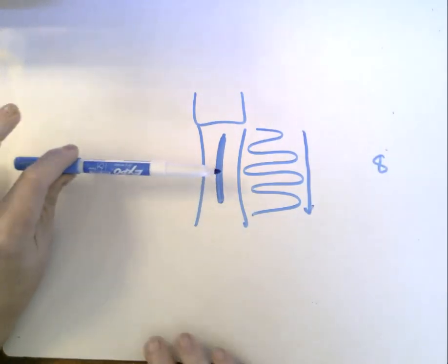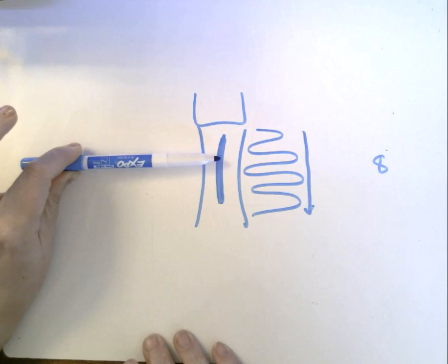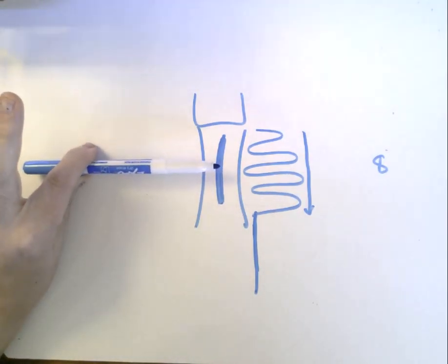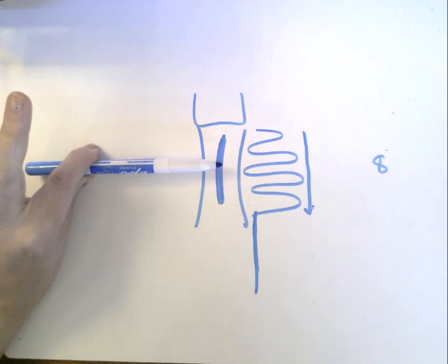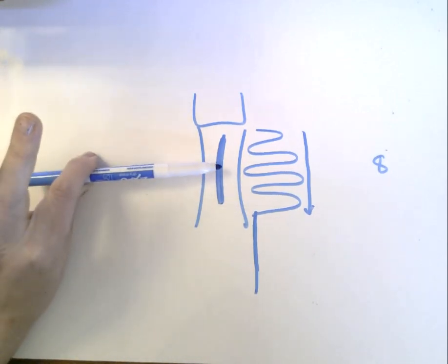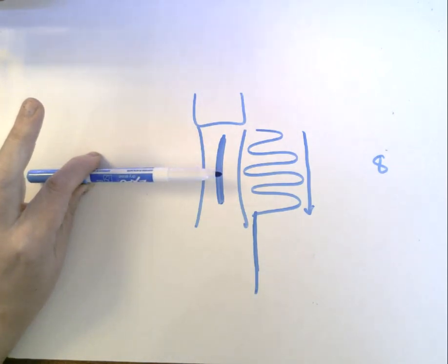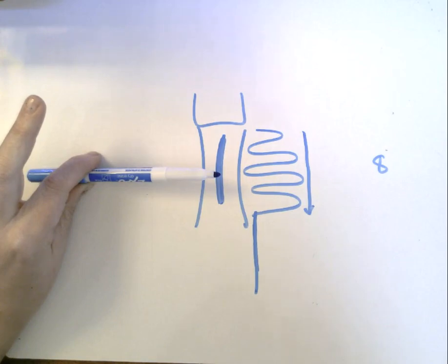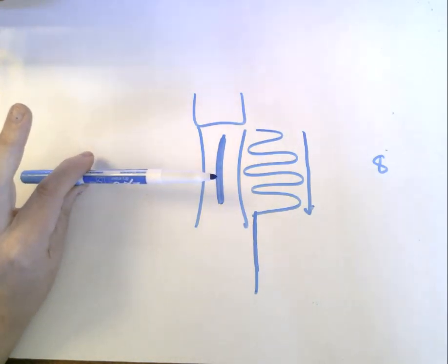We would be able to record all of the pulse as it goes by my pen. So then I could record the pulse average. And then we would also record those listening times as they go by my pen. And we would be able to calculate the temporal average from that as well. So no, as a sonographer, you will never use a hydrophone. This is probably going to be more biomed, people making the transducers, maybe physicists, if you have somebody coming and testing your transducers, but not as a sonographer. But the hydrophone is the tool that measures the intensities of the beam and verifies that we are not putting our patients at risk by using the ultrasound energy created by the machine.